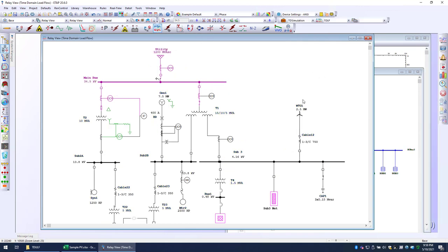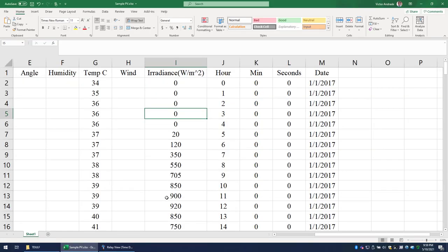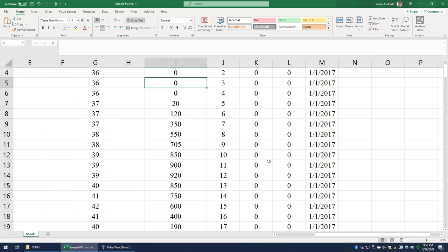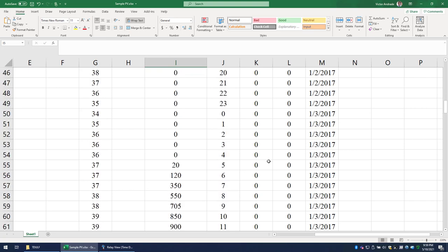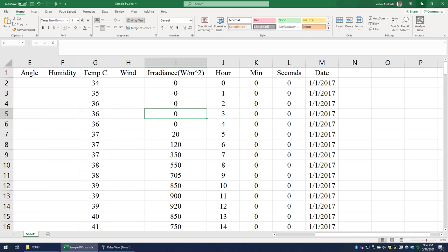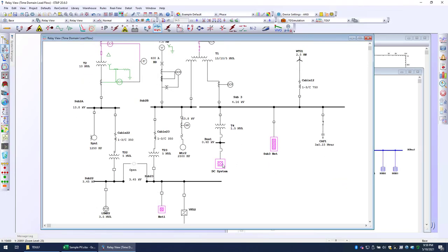So we click on the time domain load flow, and the first thing I'd like to show everyone is how we're going to attach the source information as well as the loading information. So here's a quick overview of what a solar PV source looks like. This is data that was collected over a 1 week period at 1 hour intervals, and it provides the input with temperature versus irradiance versus the time. So this is actually going to be the input for the sample PV. In the same manner, we're going to have a similar one for different loading characteristics at various loading locations.